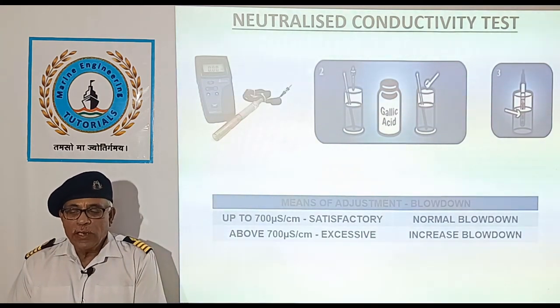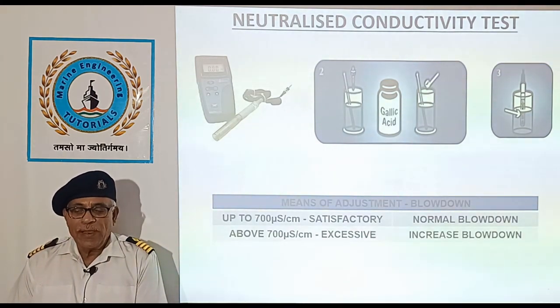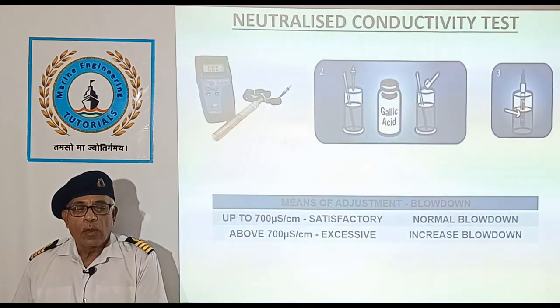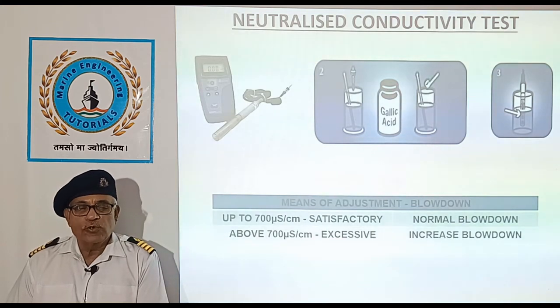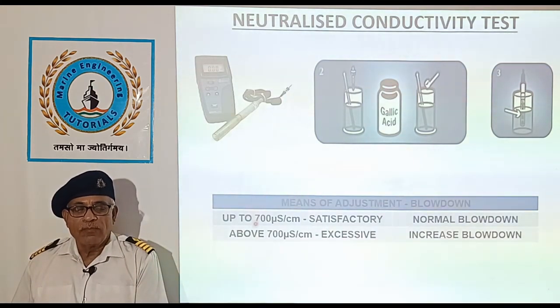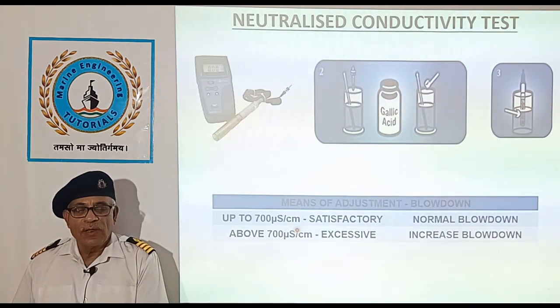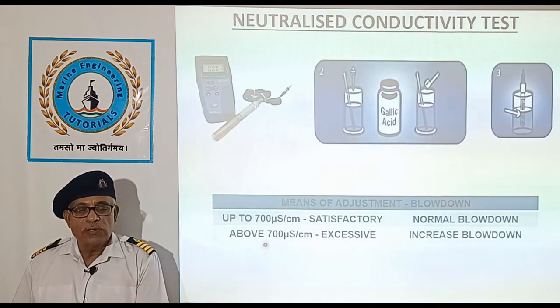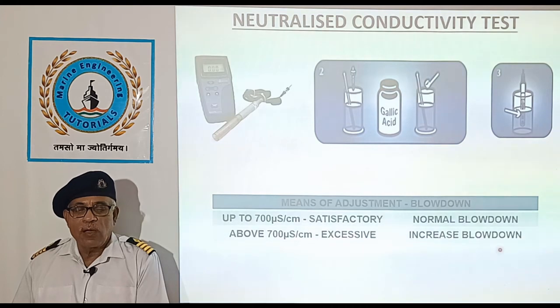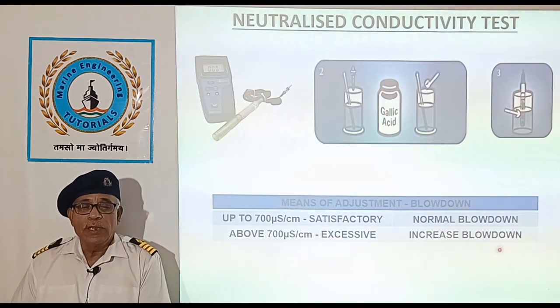Allow time for the reading to stabilize and note the reading on the display. Record the result and adjust the dosage as per the table. Up to 700 microsiemens per centimetre is the satisfactory range and we need to perform normal blowdown. But if the conductivity goes beyond 700 microsiemens per centimetre, we need to increase the blowdown to reduce the conductivity.